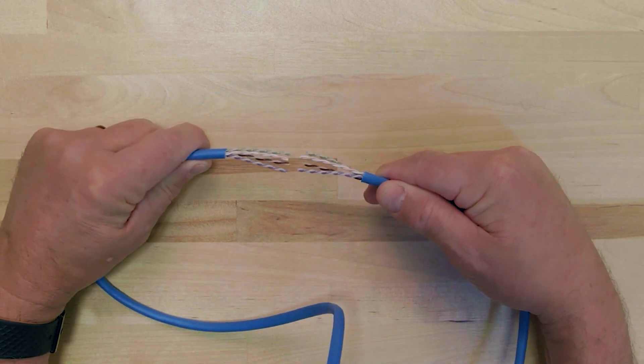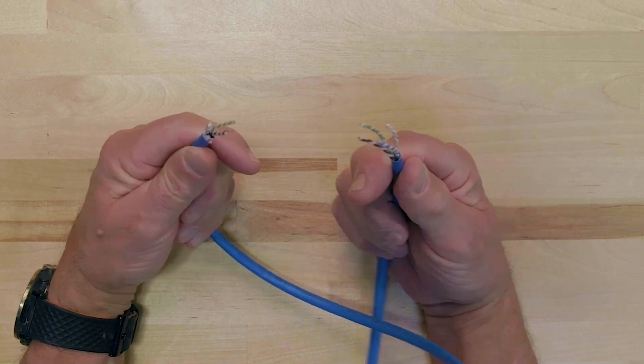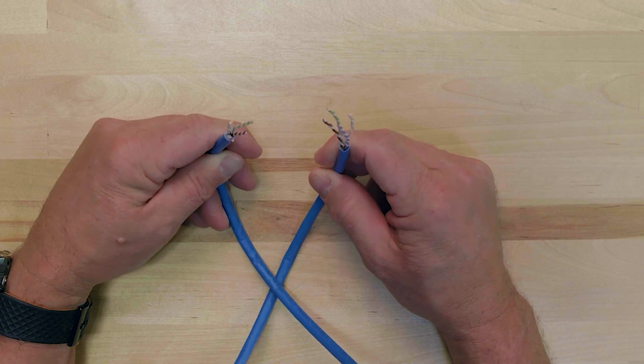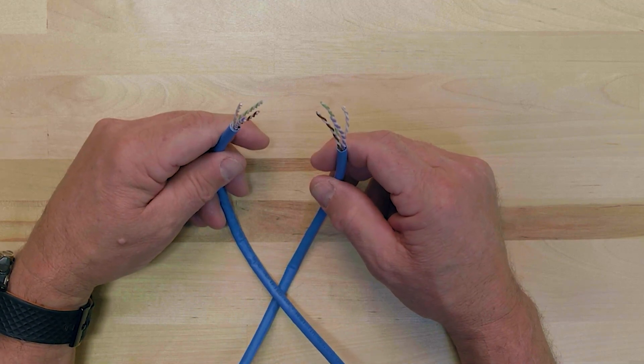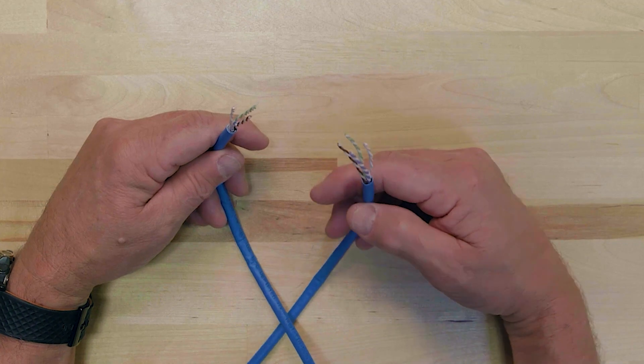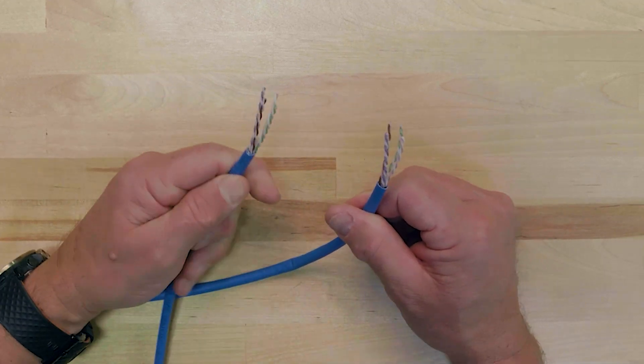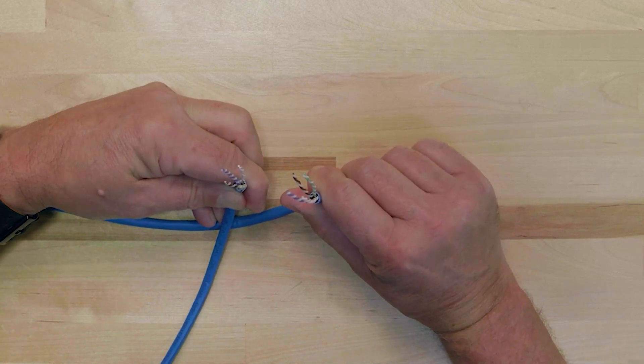When terminating any of Panduit's copper connectors, you must first begin by identifying the cable end. Begin by holding a section of cable so that it is stripped on both ends. Looking into both ends of the cable, you can see that the colored conductor pairs are a mirror image of each other, so each cable end must be terminated differently to ensure that the wires are mapped correctly.